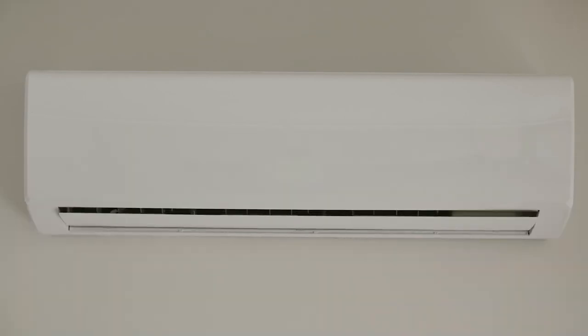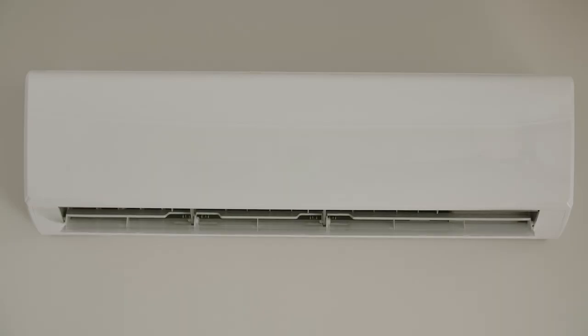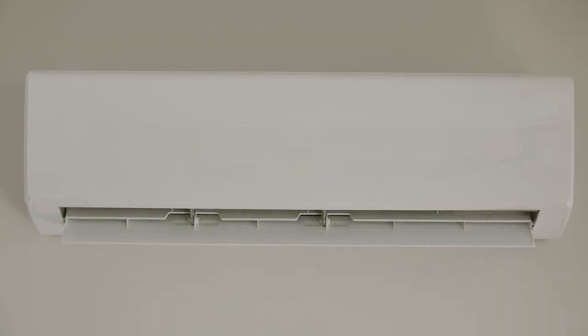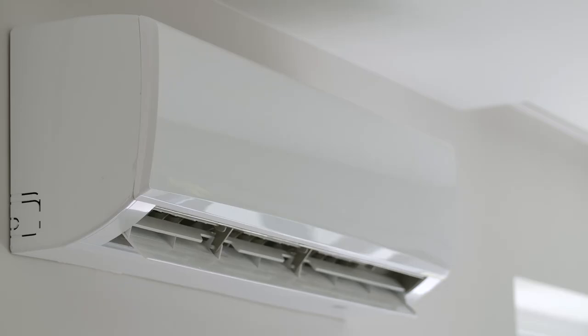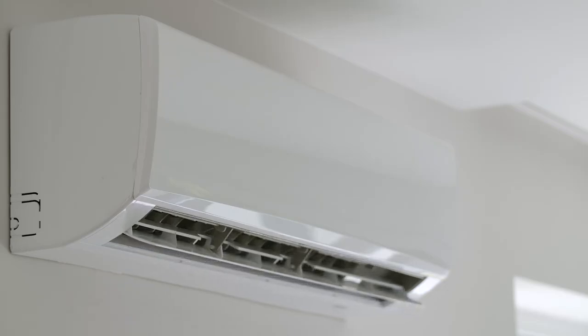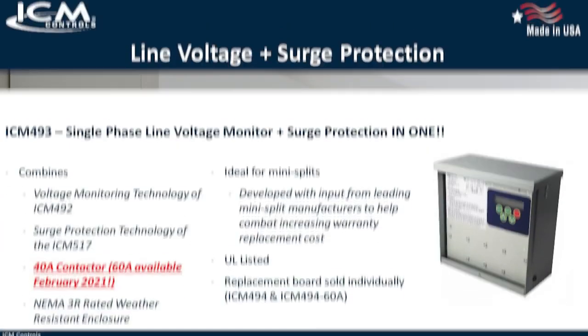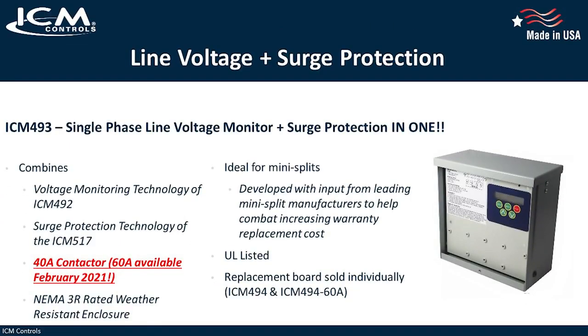You must keep in mind that some equipment, like mini splits, don't have a separate contactor. Everything is controlled through the motherboard, so there's no way to hook up a conventional voltage monitor without opening up and modifying the unit, which would then void the warranty. This makes the ICM 493 a very valuable add-on investment. However, there's also another great feature of the ICM 493 that makes it especially ideal for protecting mini splits, to the point where most major mini split OEMs actually recommend this product to protect their system.